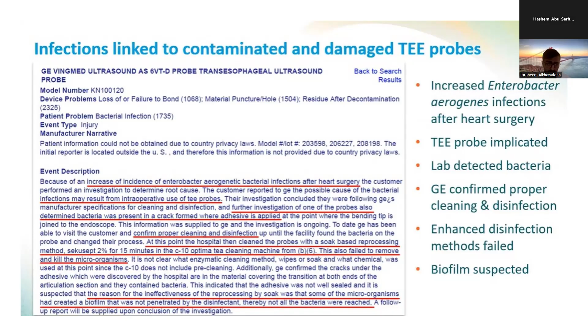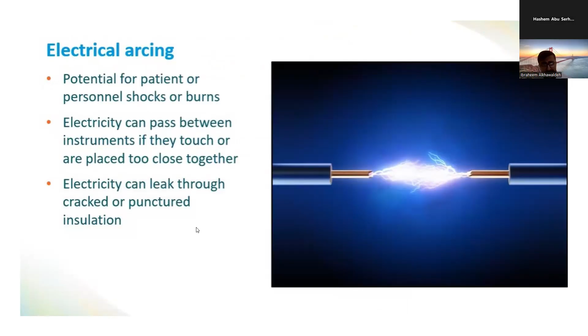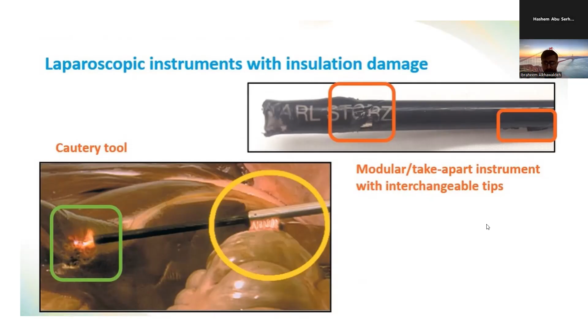Our next problem is electrical arcing. As you know, it can happen in surgeries and it can lead to potential patient shocks or burns. The electricity can leak through cracked or punctured insulation, as you can see. So I asked myself, here's an example that happened. There is damage to the insulation, and the instrument shows the damage itself, and you can see the arcing from the cutting tool in the second photo here.